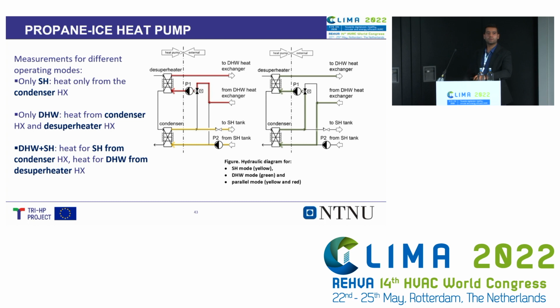The system is also able to work under space heating only, domestic hot water only, and the combined mode. Here we have the schematic for the unit. The inlet of the desuperheater is the outlet of the compressor. The refrigerant passes through the desuperheater and the condenser and goes to the evaporator. We have the counterflow here. This is the concept: only the green one when we want to use the system for domestic hot water production. We use the condenser as the preheater and the desuperheater as the reheater for production of domestic hot water.